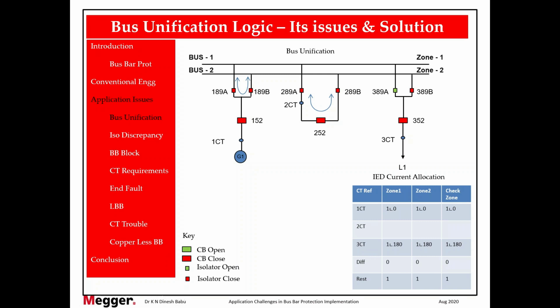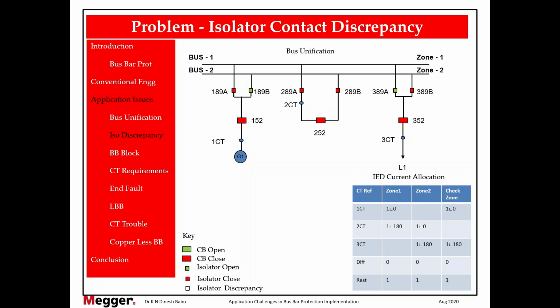Okay, next part, isolator discrepancy. So let's go back to the same example. We are feeding bus 1, through the bus coupler, and feeding out through bus 2. Now the problem is, suppose I have written a key here. Isolator discrepancy means no color. So now for this isolator, I have removed the color. That means there is a discrepancy. The discrepancy means physically the isolator is closed, but the relay is not getting feedback. It is a very common problem occurring in many stations, so numerical relay technology has to take care of it. How will it take care?